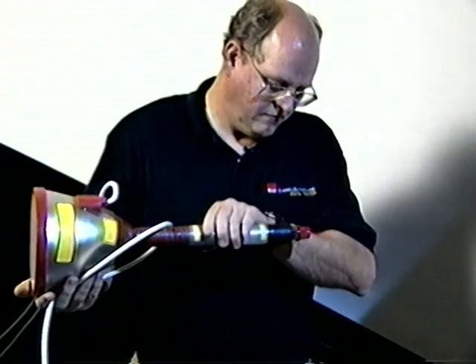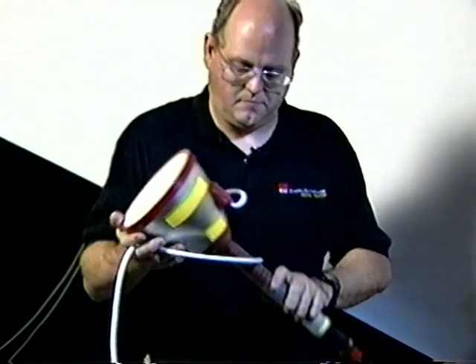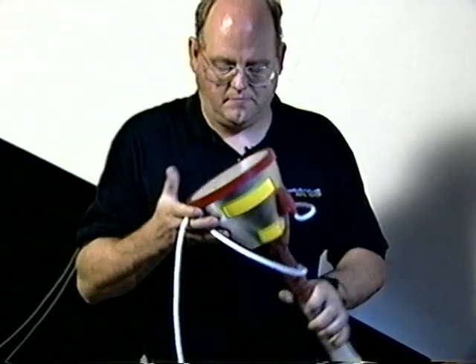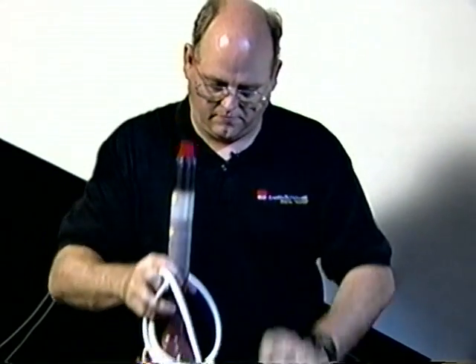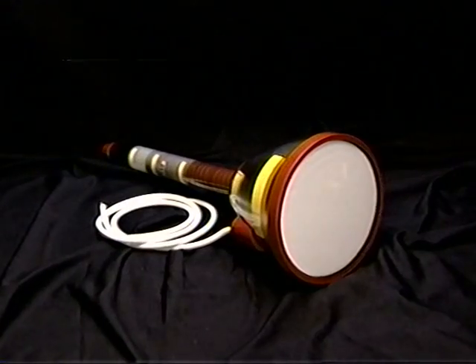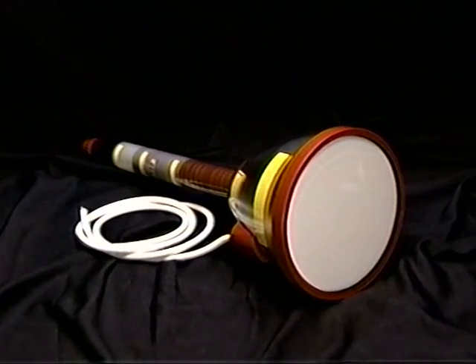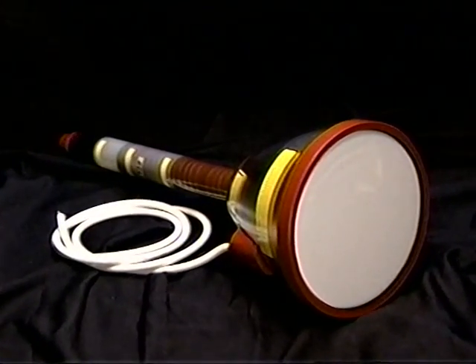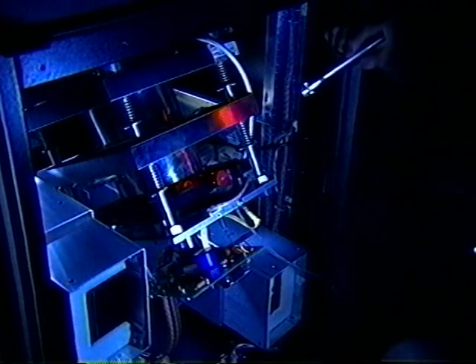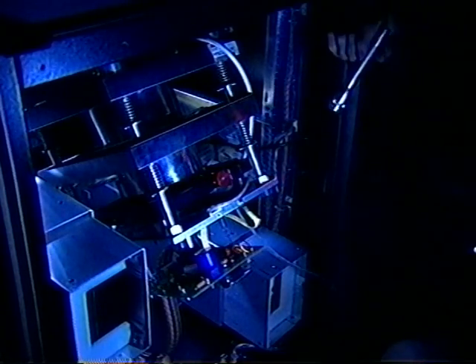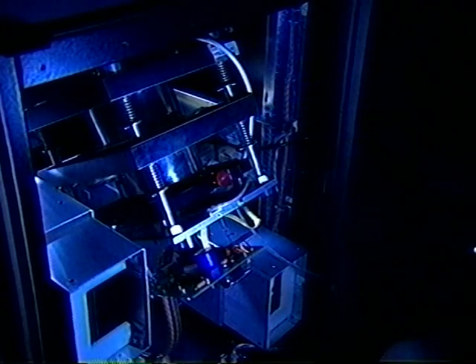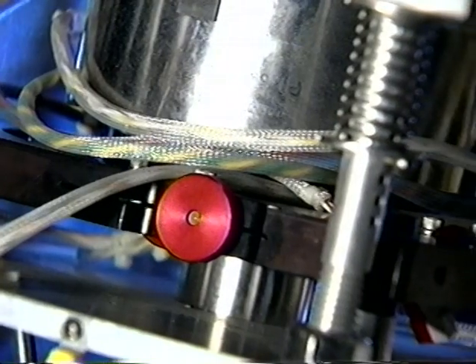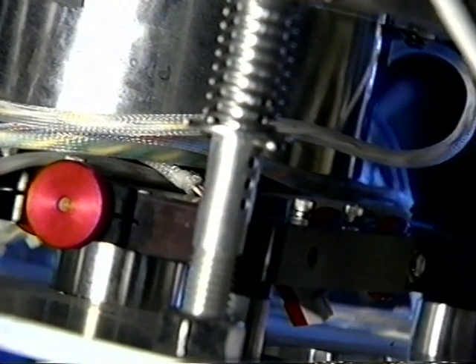When handling the CRT, be aware that it can develop a significant static charge. This is similar to the shock you get walking across a carpeted floor and touching a doorknob. Although not harmful, the discharge can startle you enough to injure yourself or drop the tube. Never operate the CRT with the X-ray shielding removed. The metal shielding in the no-pot CRT assembly prevents exposure to harmful radiation from the CRT.